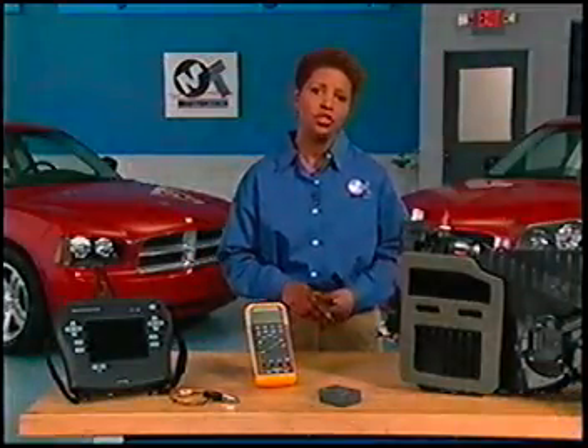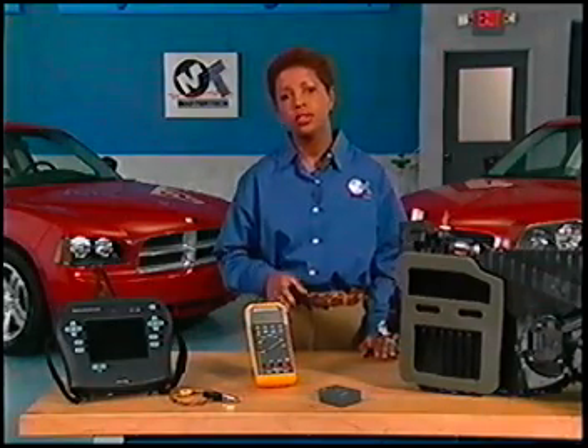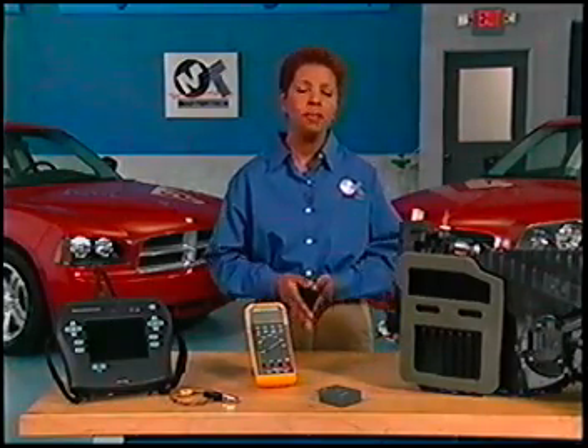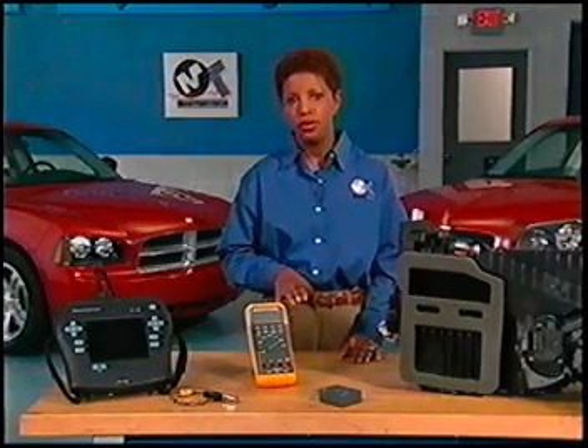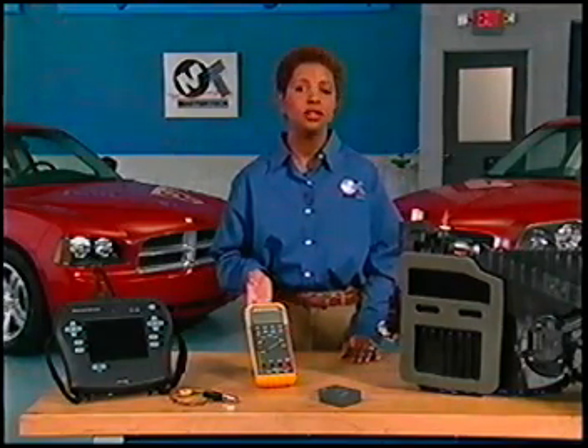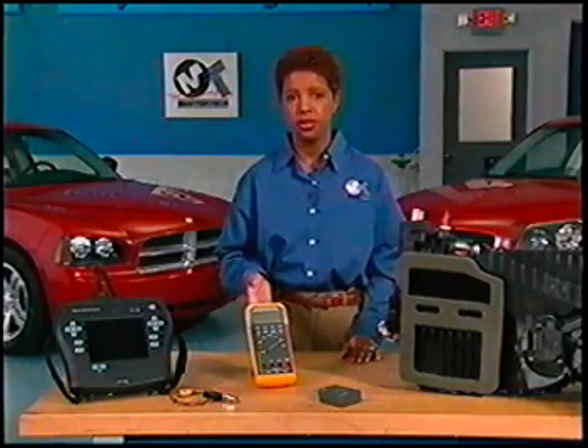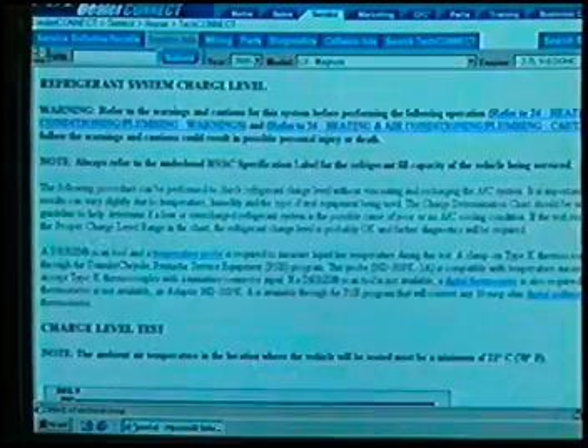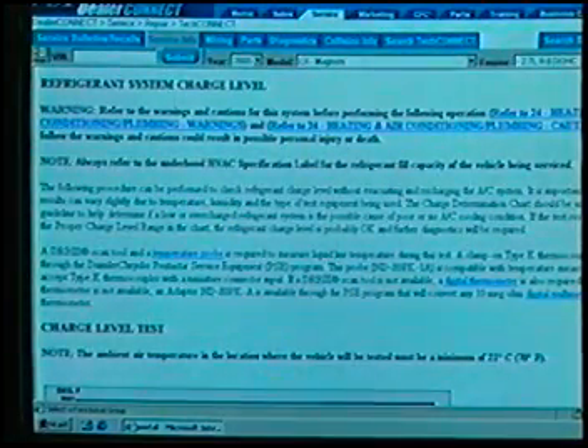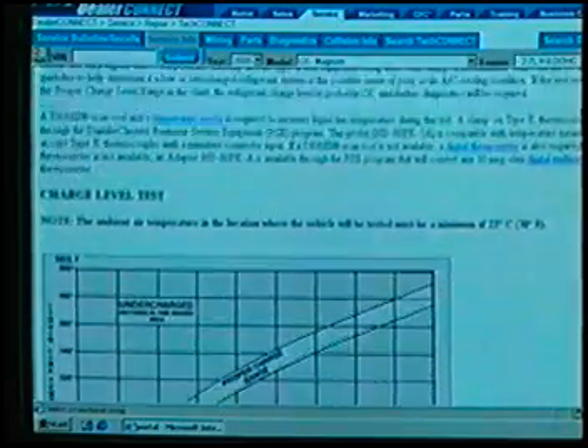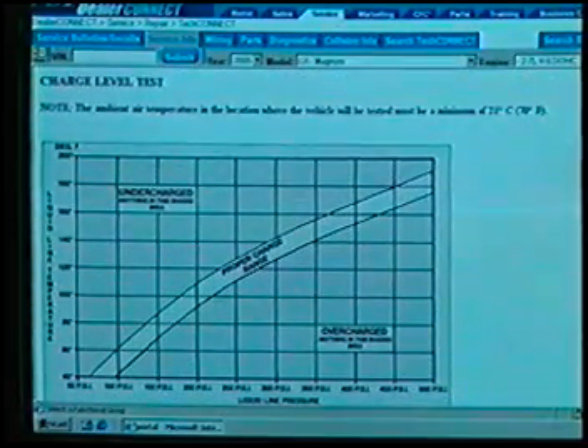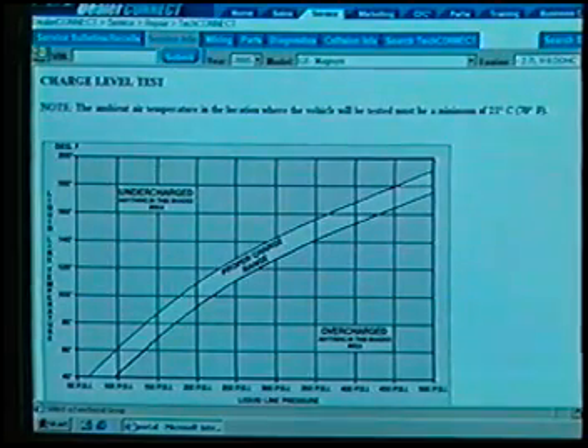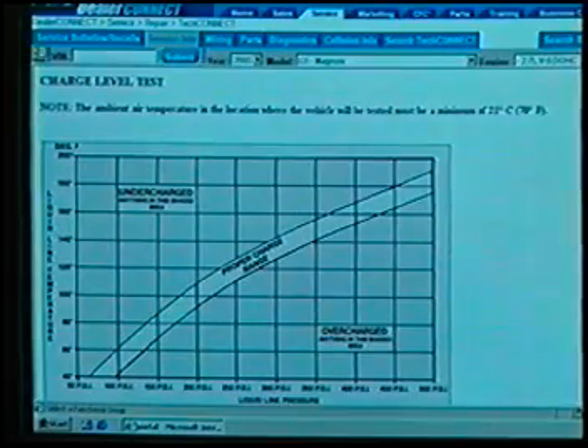Not all of the changes in HVAC diagnosis are the result of new models. For example, recently, the test used to determine whether an AC system has the correct amount of refrigerant was revised. You can use the revised partial charge test as a general indication of whether a system has the correct charge. You might use this test after an AC performance test indicates that the system is not operating as it should.